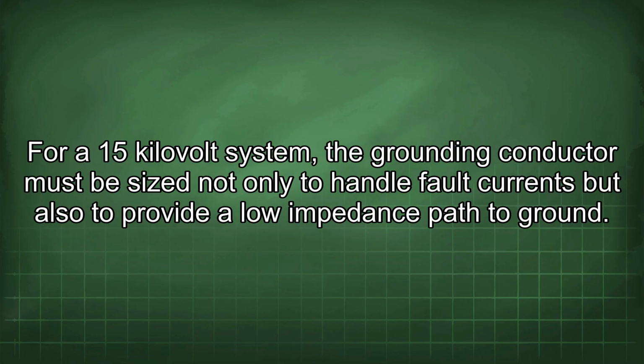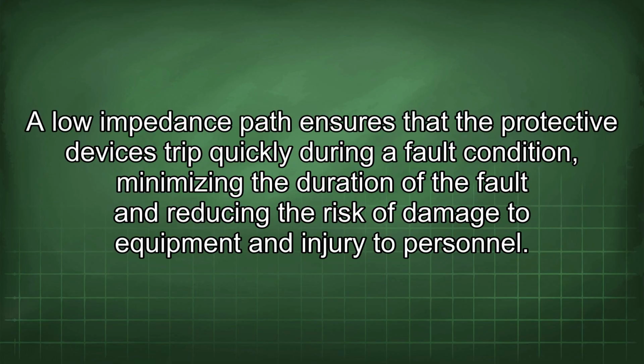For a 15 kilovolt system, the grounding conductor must be sized not only to handle fault currents but also to provide a low impedance path to ground. A low impedance path ensures that the protective device is tripped quickly during a fault condition, minimizing the duration of the fault and reducing the risk of damage to equipment and injury to personnel.